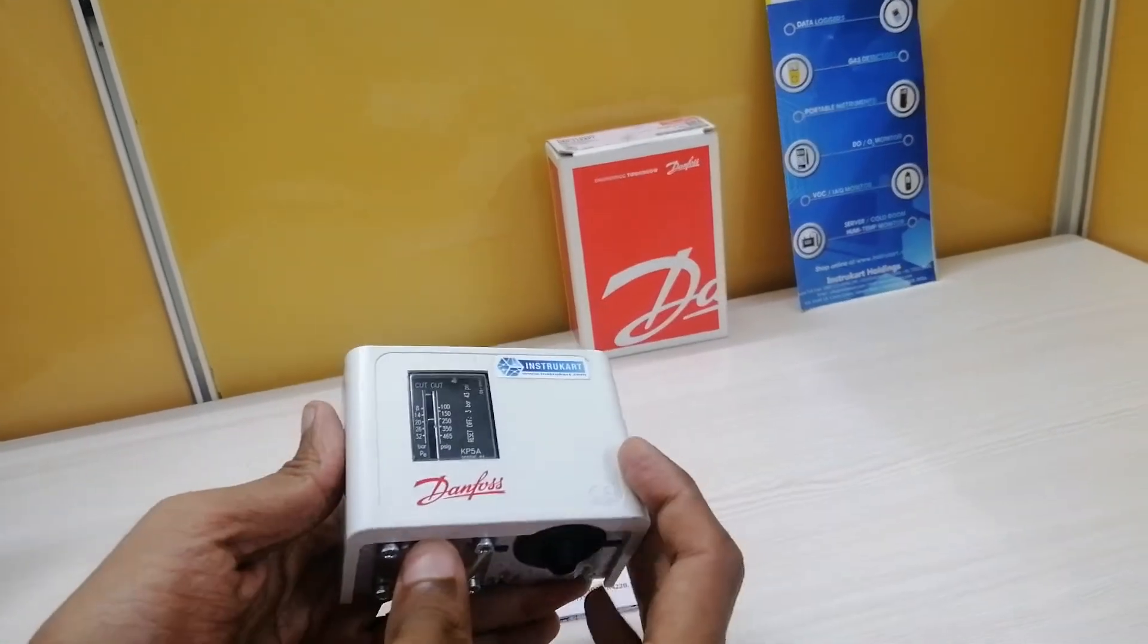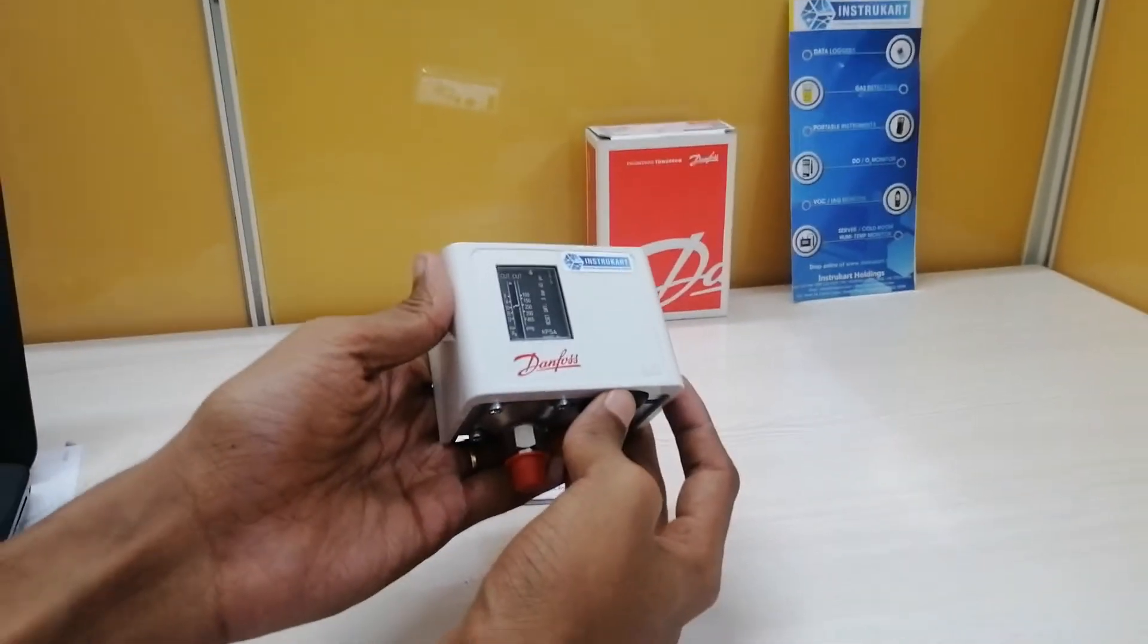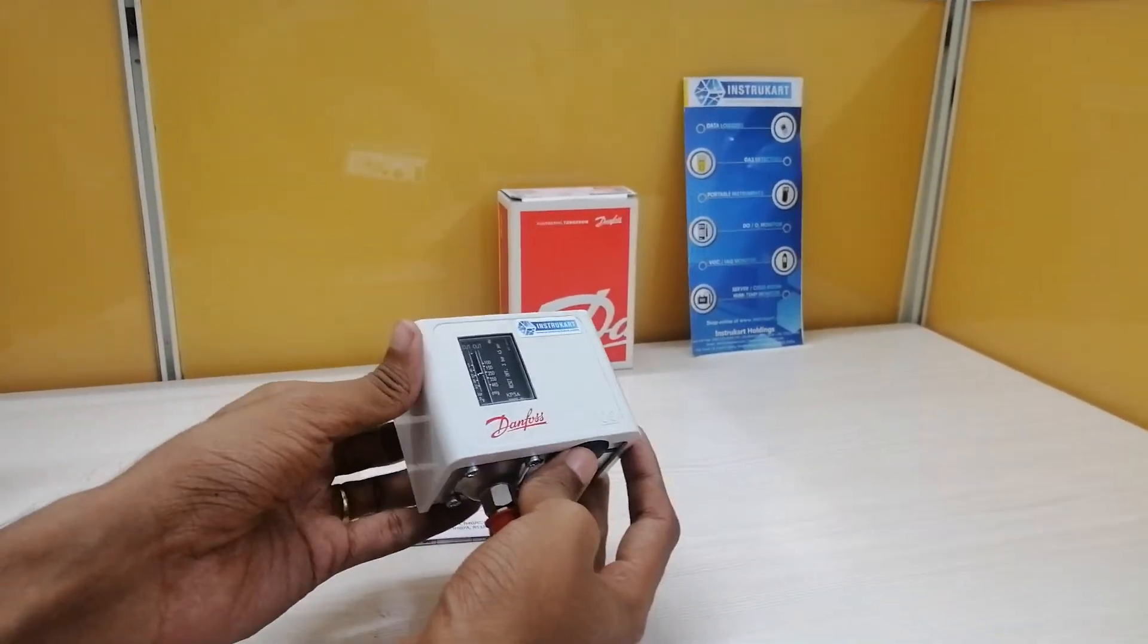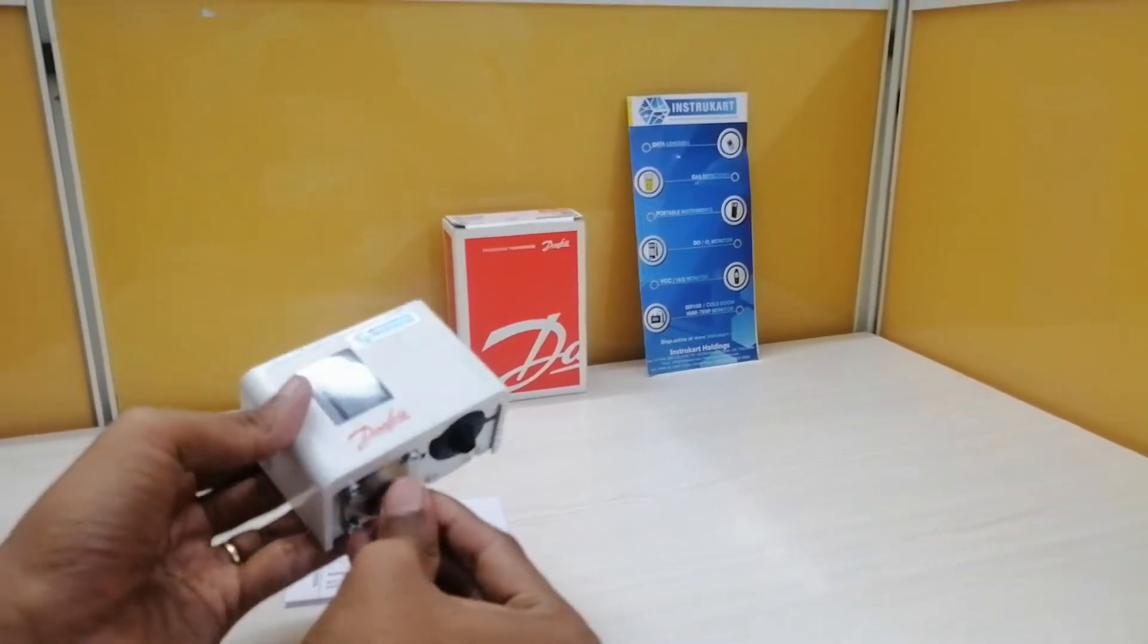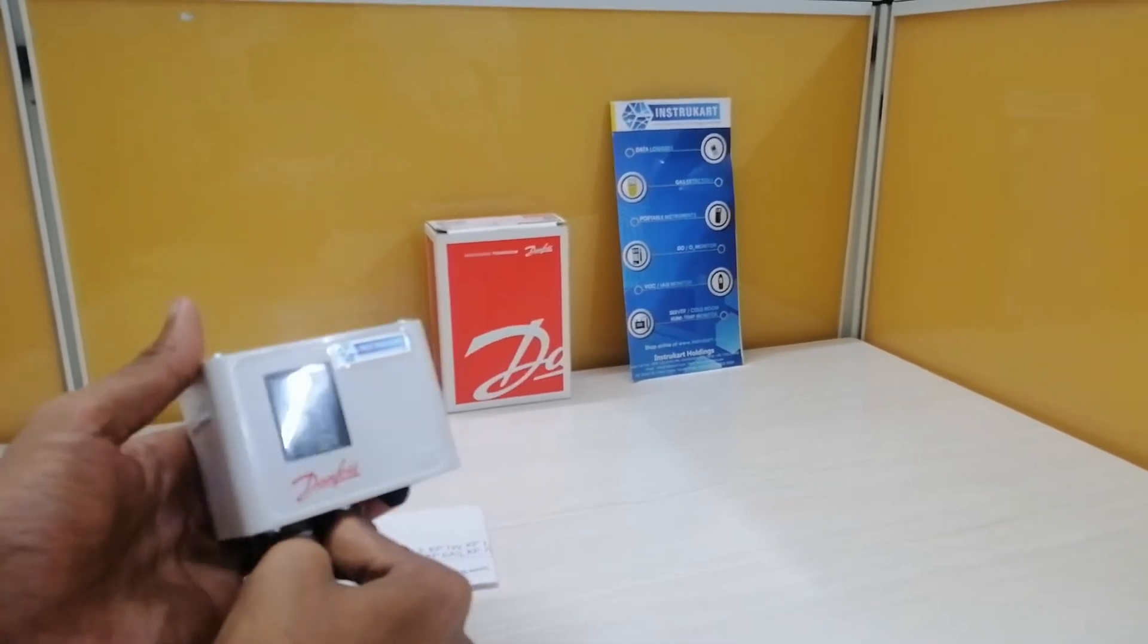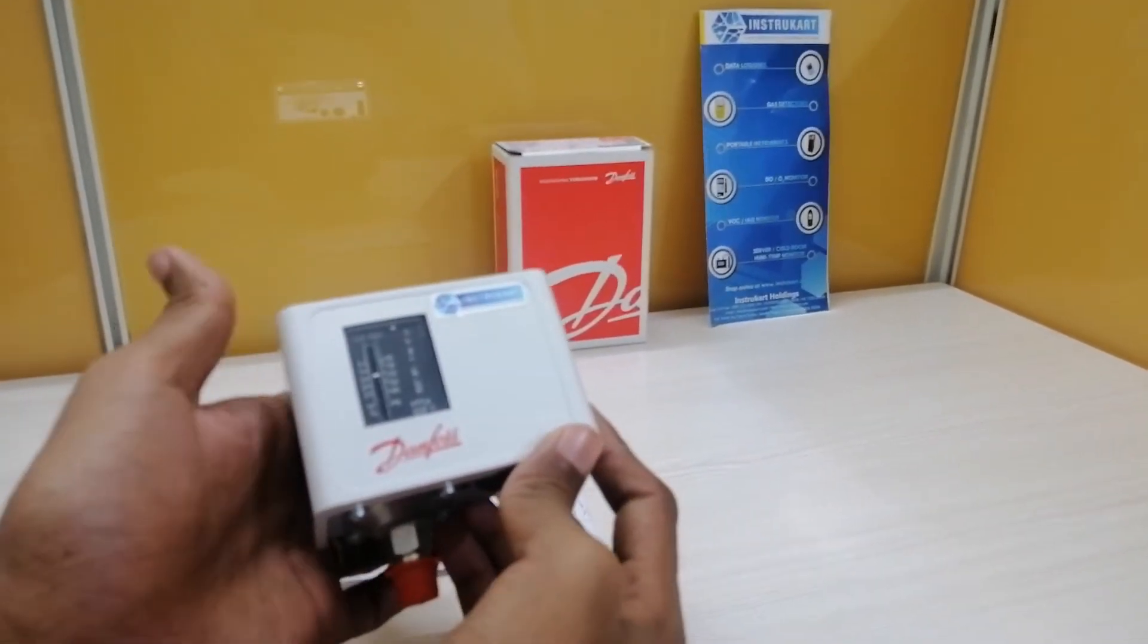These pressure switches are designed to protect refrigeration systems from excessively high discharge pressures, excessively low suction pressures, and are also used to start-stop compressors or to operate fans of air-cooled condensers.